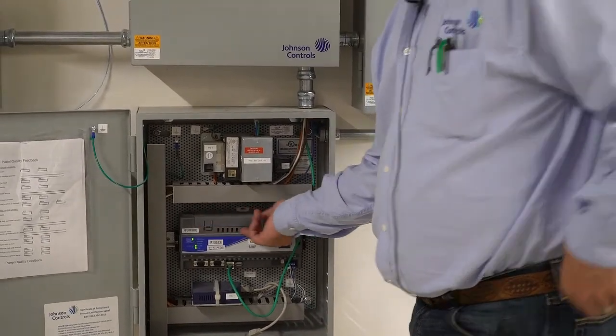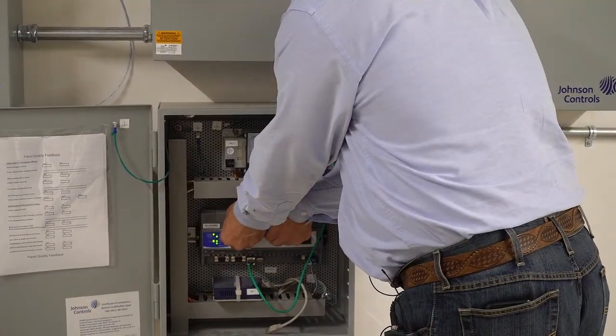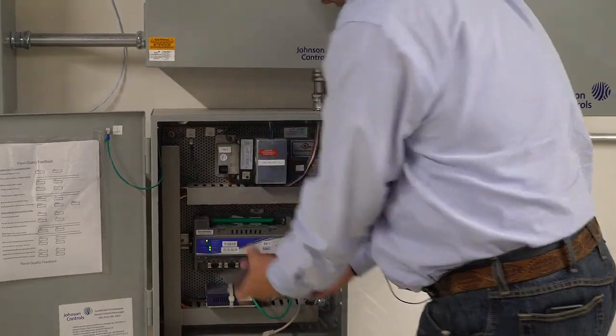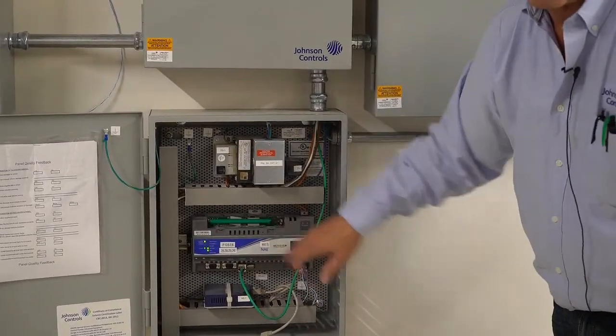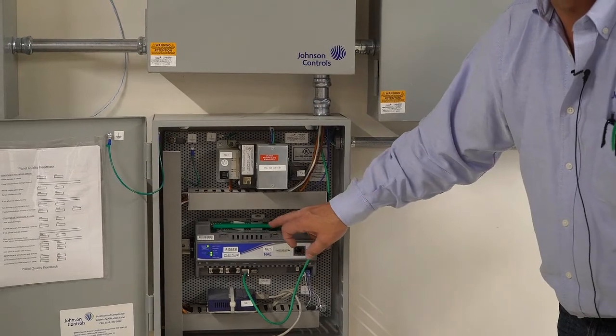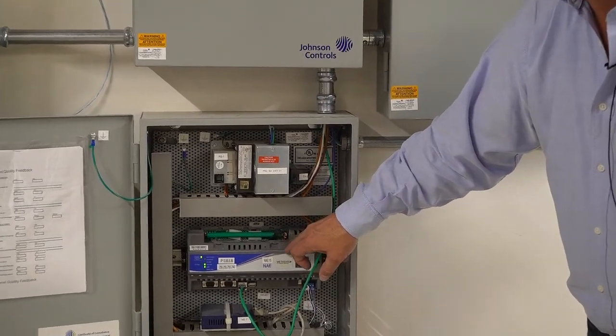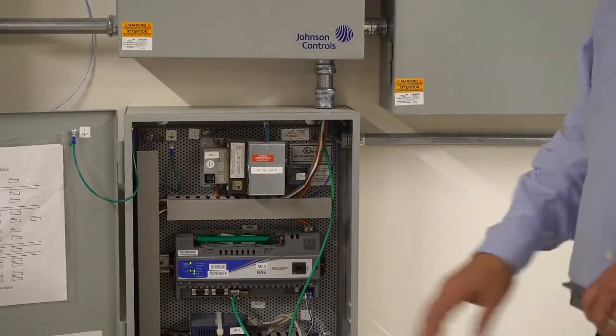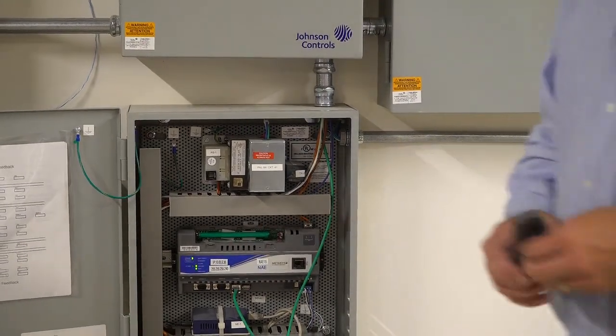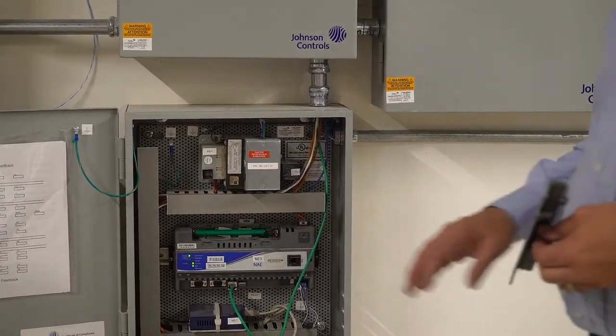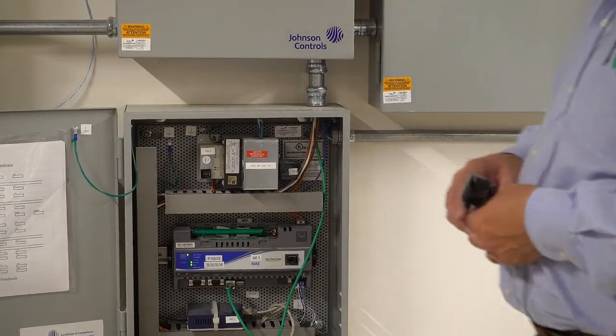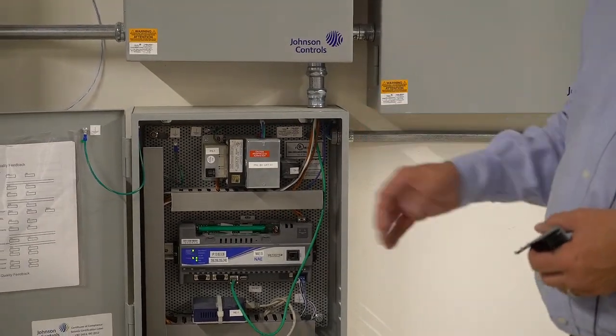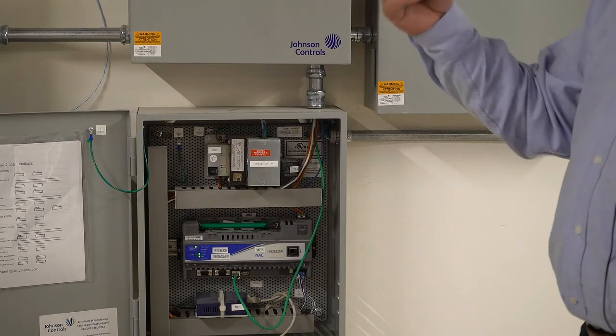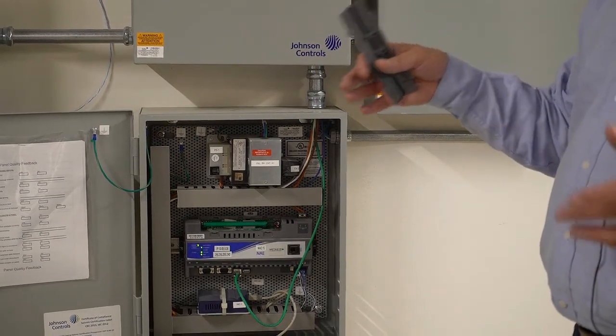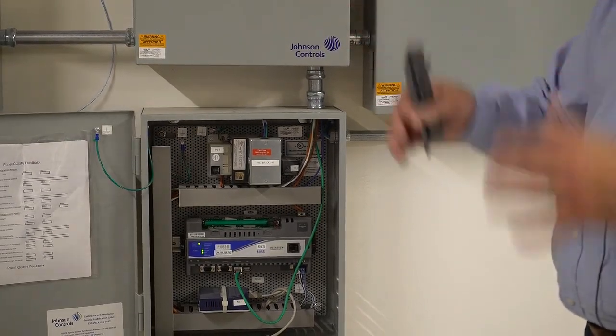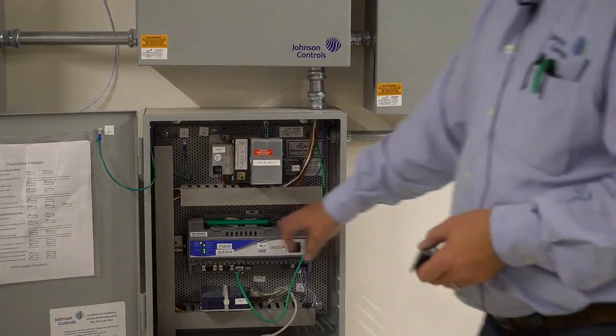These do have batteries in them. They're just a small battery. They do recommend at least every 3 years to change these batteries out. These batteries are not for power outage usage. The purpose of these batteries is to give the unit a controlled shutdown. So it's similar to a computer. If you lose power, you usually have a backup on there for like 5 minutes or something, so it can do a controlled shutdown. That's the purpose of these batteries.